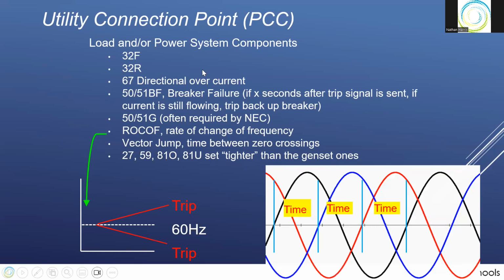At the PCC, the point of common coupling, the utility tie point, you want to do such things as 32F, 32R, that's power out and power in at that point. You may want to think about those. Directional overcurrent may be required by the utility. 50 breaker failure, that is if you send a trip out and it doesn't make it, then you need to trip the next breaker up line. So that's a 50BF. 51G is often required by the NEC, ground fault protection.